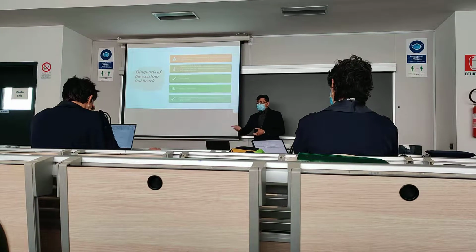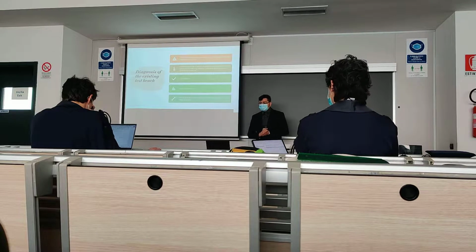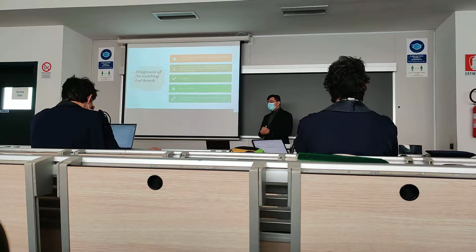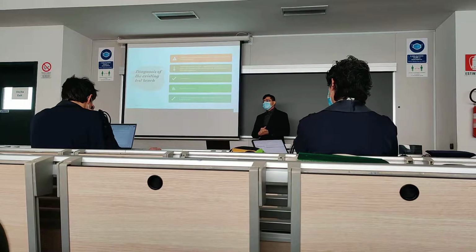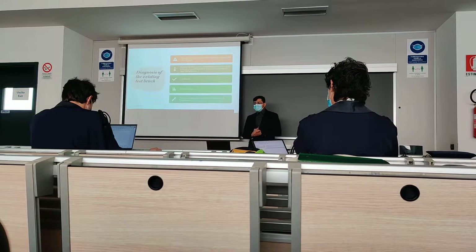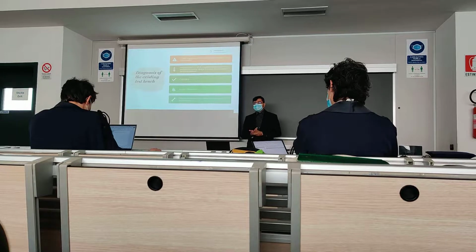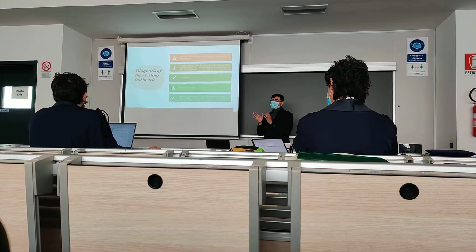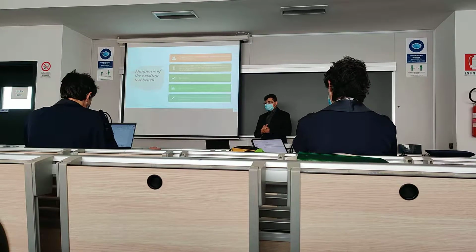And then we did an experimental analysis using a pressure measuring device. This pressure measuring device is of very high accuracy and precision, from TSI Instruments. With this we checked the static pressure and also the total pressure. The static pressure transducer had some issues, and the total pressure transducer also had some issues.